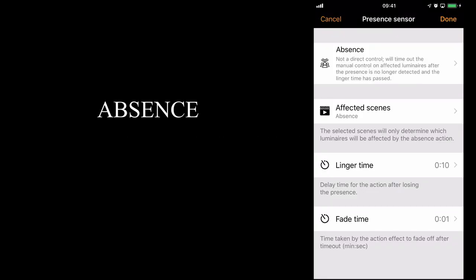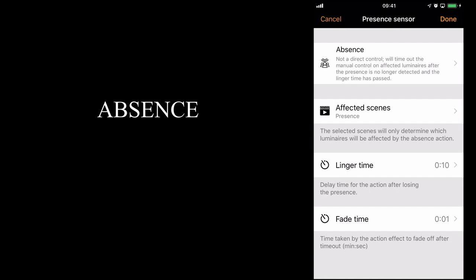The absence option doesn't actually control luminaires. It simply waits for an absence within the room. I'll select my presence scene. I have the same linger time of 10 seconds, and a fade time of 1 second.